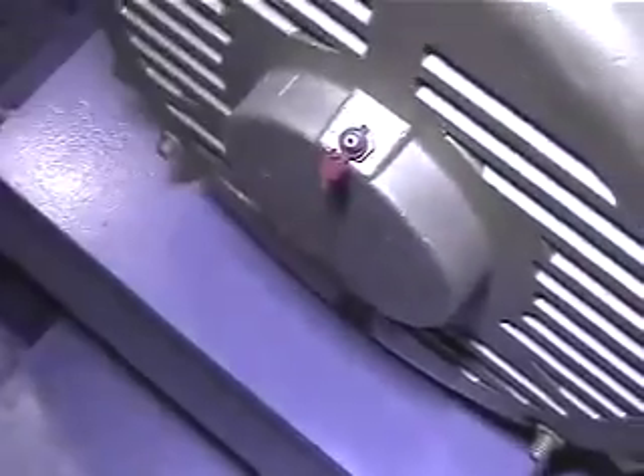On the fans for this unit, you've got two VFDs over here on the wall. They're bigger boxes than the other ones that were in the training, but inside is basically the same. And instead of having one fan, you have something called a fan wall, or 6 fans, and they're all direct drive. The fan blade is mounted to the shaft of the motor, and there's a grease zerk right here, and then another one right up front. Once a year, or however you normally maintain your fans, don't over grease them. That's worse than under greasing. On the other side you can see their screens, so you can't put your fingers in there, but you've got the fans running and maintaining the pressure. And if I understand correctly, the top 3 are on one VFD and the bottom 3 are on the other VFD.